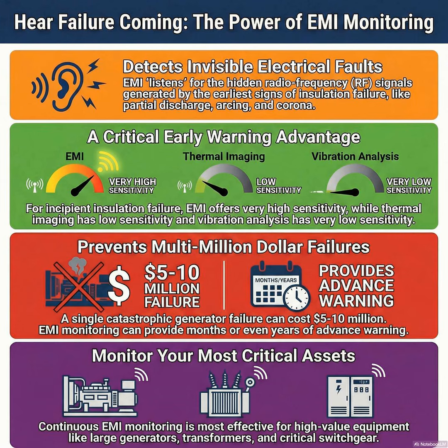Well, the key fault mechanism here is something called partial discharge, PD for short. This happens in the solid insulation materials, the stuff wrapped around the big copper windings. Over time, tiny microscopic voids or air pockets can form inside. And when the voltage across that little void gets high enough, it ionizes the gas inside it, creating a tiny, temporary conducting channel.